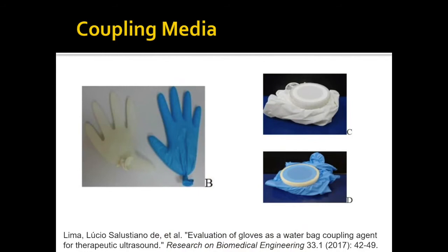More creative solutions that I've recently come across—this is a paper from 2017. If your transducer or your target is irregular for whatever reason, and you want something more resistant to shearing and distortion—our gels that we cut, for example, will fracture and break if you move the transducer too much. With this kind of paradigm, what they've used is simple latex gloves. They've stretched the latex glove over a little ring, a 3D printed ring or a ring of plastic, and filled it with deionized degassed water. Based on the experiments here, they've shown that this is just as good as immersing your transducer in pure water without any physical coupling medium, which is really good. We haven't tried this, but it's something to look into.